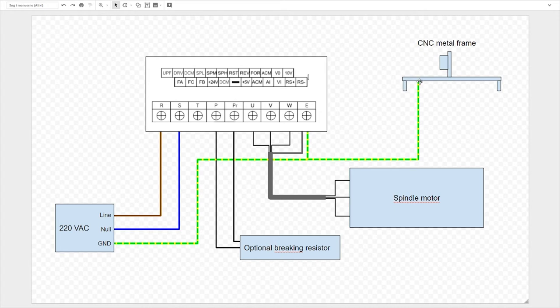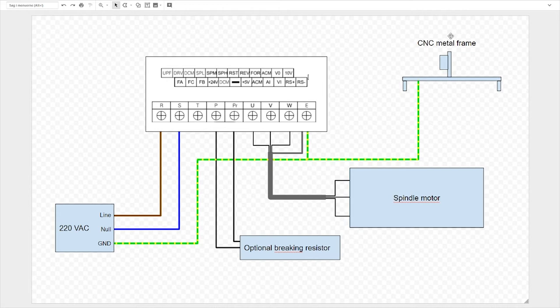In my case, I can connect line and neutral in any combination to R, S and T and then ground or earth is connected to E over here, which is earth. And it's also connected to the frame. So I basically have wire that is bolted onto the frame. This is because if any one of these wires are damaged, so there's like 220 volts on the frame, then it's immediately gonna go through earth and your RCD relay will shut everything off. The reason you connect ground to the frame is so you don't get shocked if anything goes wrong.